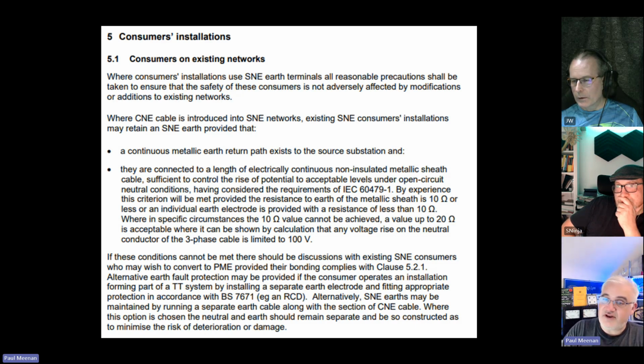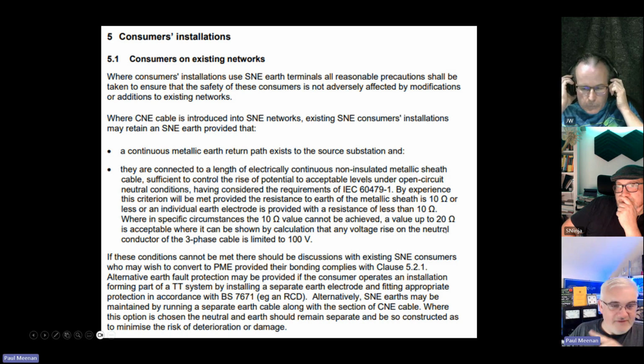And that's exactly what they did with Eddie. They dug up a cable, couldn't find a fault. So what they did was they just put loads of electrodes in to reduce that step potential. And this is at a church. Now, if that doesn't tell you, you could ask them, how can you assure me via calculation you won't get above 100 volts? They can't tell you. So I think it's fair to say, and I know John's probably going to mention this as we go on. Let me finish though.